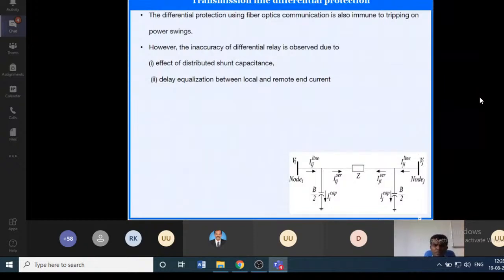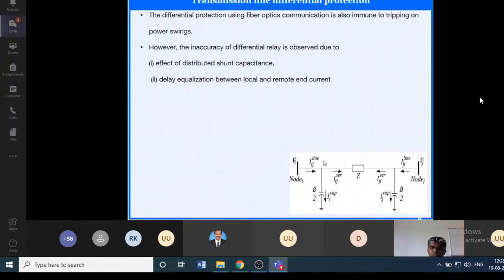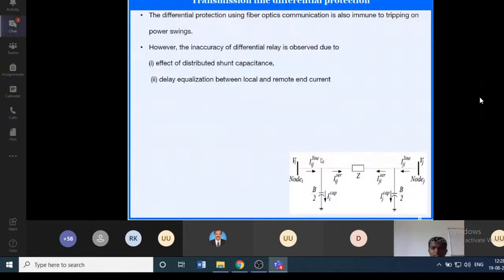The transmission line has distributed shunt capacitance, right? That will introduce a shunt capacitance current, which will produce some additional time lag in the current signal. Then the delay in the equalization. What is meant by equalization? Actually we are going to send data between two buses, the I bus and the J bus. This current signal will be sent to the other node, and similarly that current signal will be sent to this node. When you send this current, the fiber optic communication will take some time delay. That time delay will be accounted for, equalized, using some components at the remote end. It will not be constant; it will vary with respect to the operating condition.